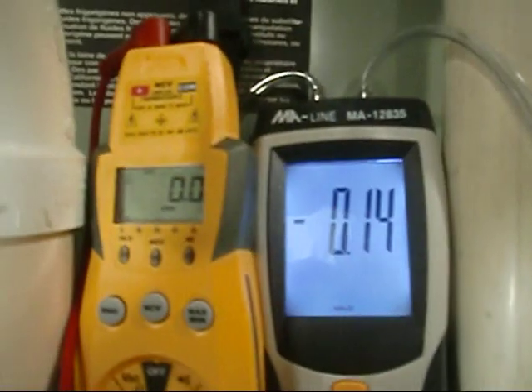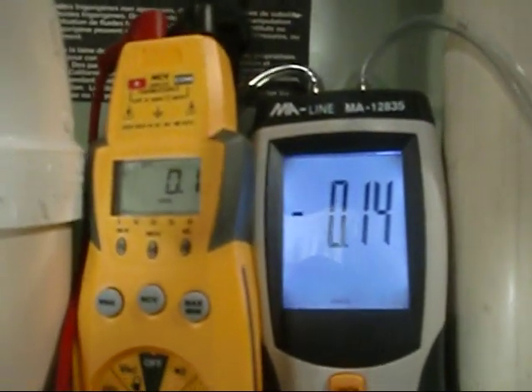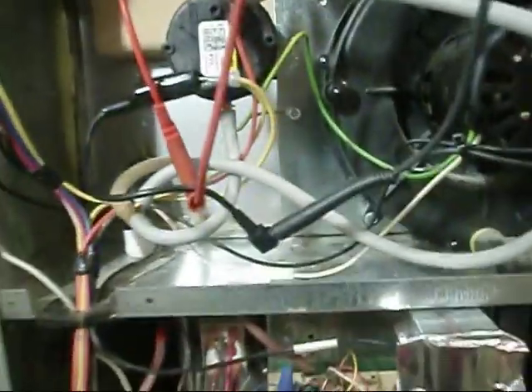And on the other side of this T, she's feeding back. She actually T's right here, goes into the gas valve here. And the other side, this reference tube right here, she feeds directly into the burner box there. And on the negative side of the manometer here, we've got her feeding right here. We've got the nice new little T here hooked to the bottom of the pressure switch here. And the other side of the T is hooked directly into the secondary heat exchanger.